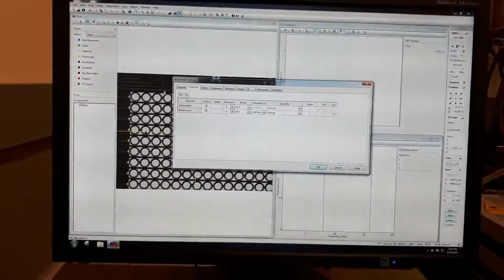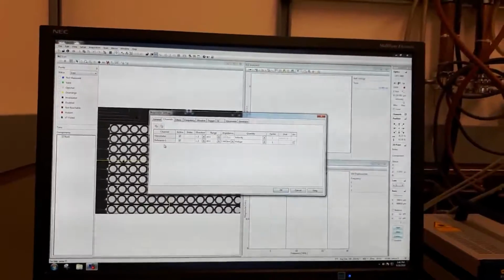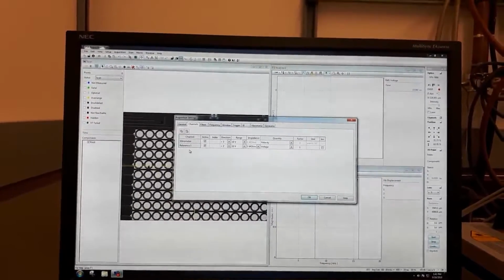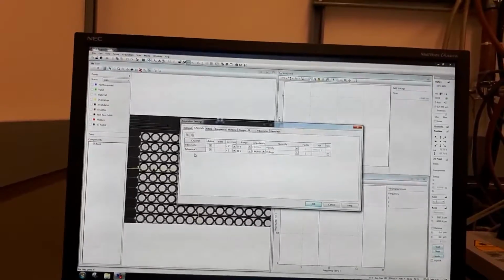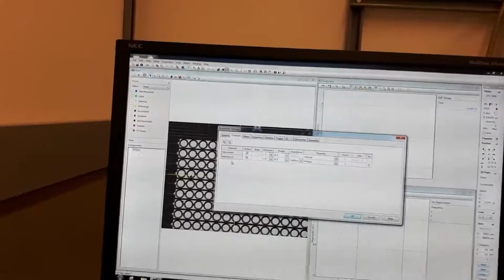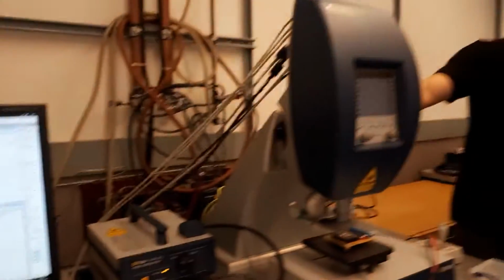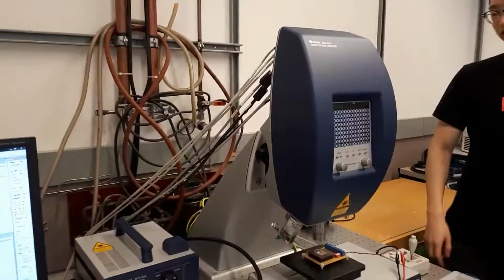There are two different rows here: vibrometer and reference. The reason we have that is that in reality we have two laser beams, and this system can be used in the differential mode. So you can have a moving structure within another moving structure and still capture the movement. The reference signal is connected to a mirror, which is behind that scanning head. So it's not connected now.